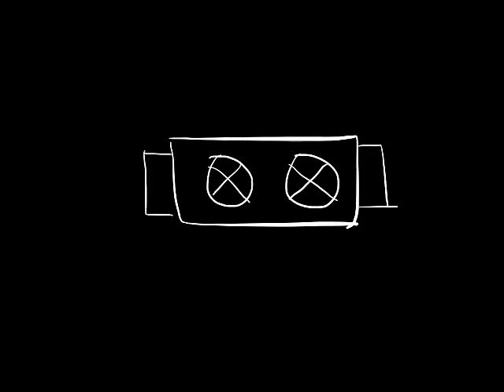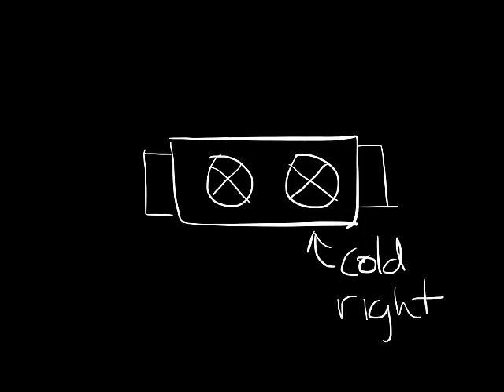You determine the hand of a dual duct box based on where the cold air inlet is. So if the cold air inlet's on this side, it's right-hand. If the cold air inlet is the other side, then it would be a left-hand box.